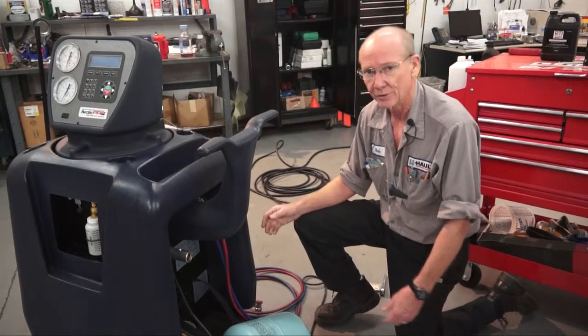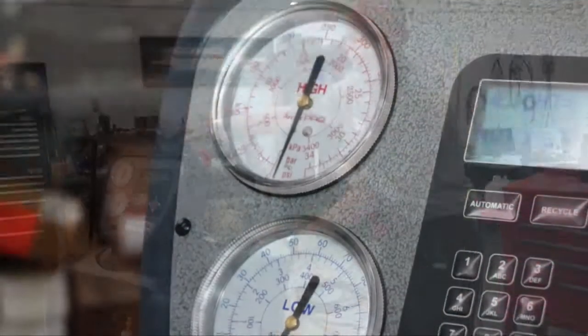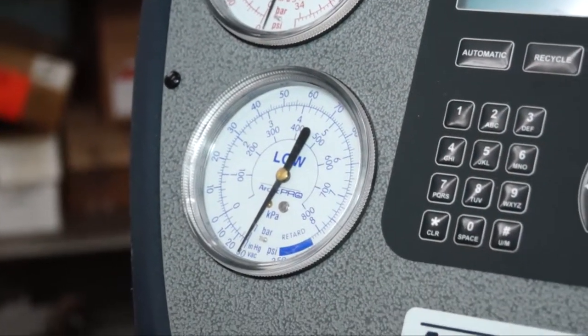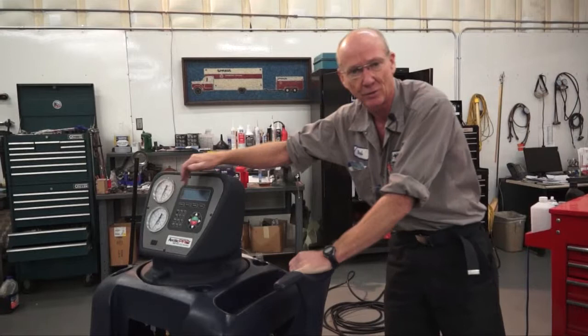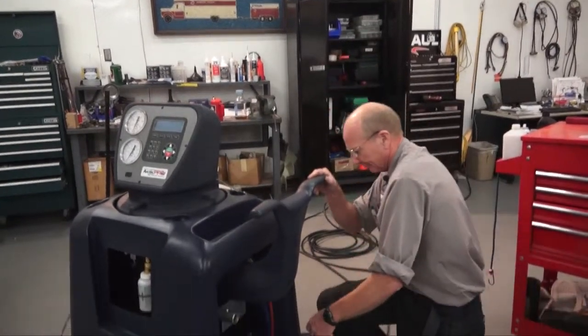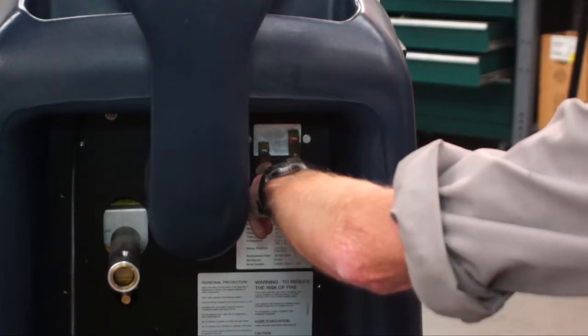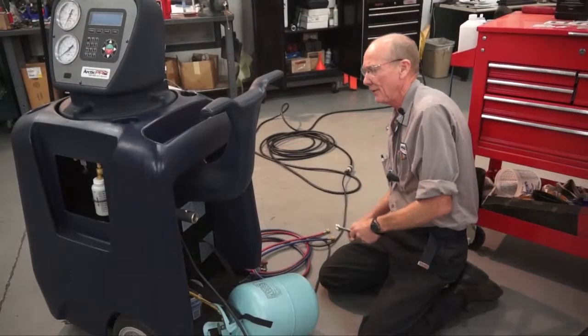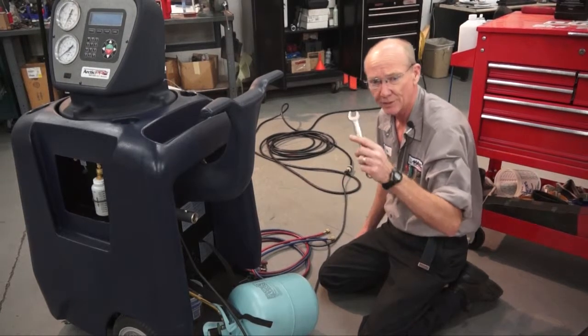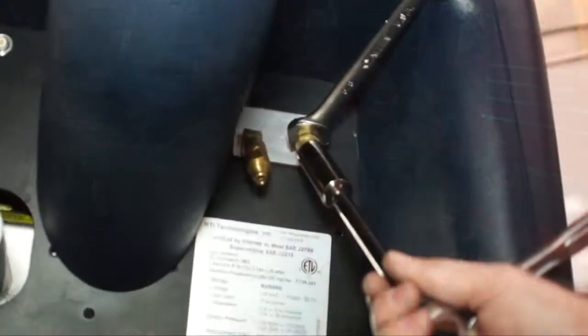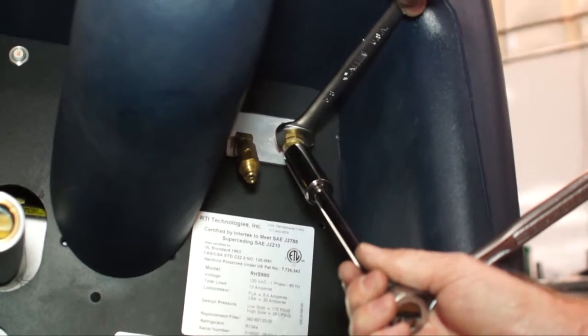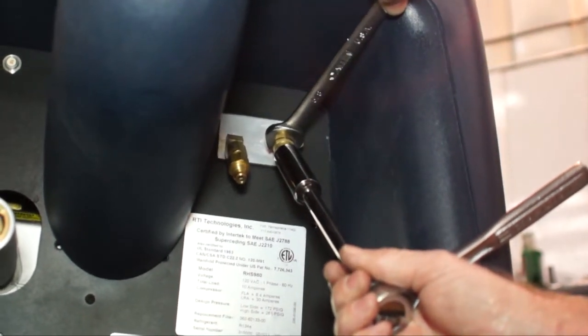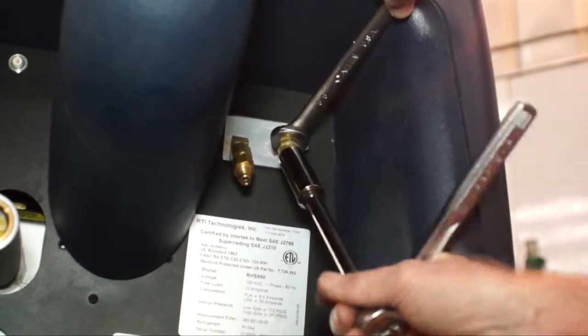So the first thing I want to do is make sure that my gauges are at zero. There's no pressure or refrigerant inside those hoses. You just look at your gauges. They must be zero or below. And I'm going to unscrew the service lines. What I'm going to do is unscrew these brass fittings that house the inline filters. So I'm going to take a 5/8 inch open end wrench, and I'm going to use that as a backup wrench because I'm going to hold the top fitting in place. We don't want that to turn. And I use a 5/8 deep socket with an extension to get it out of the way of the handle. Okay, loosen those up.